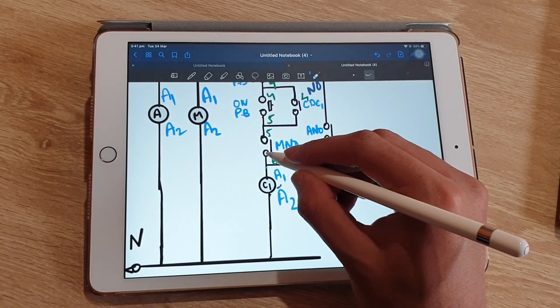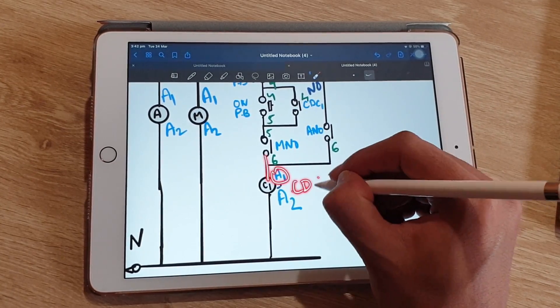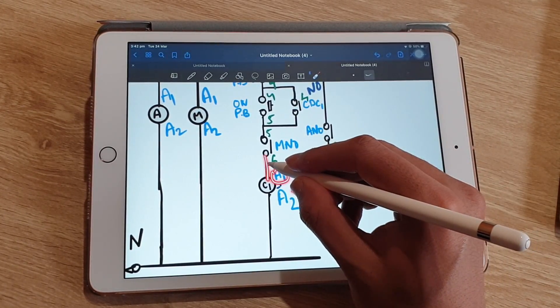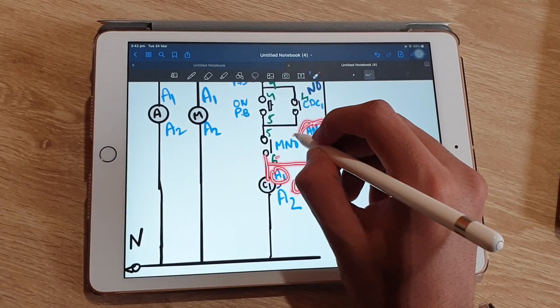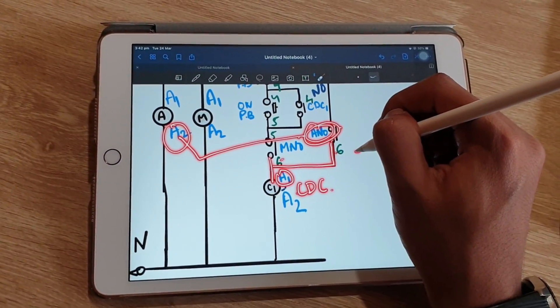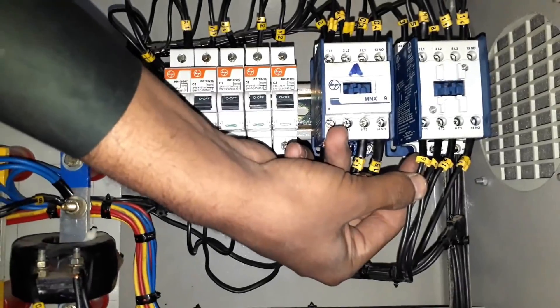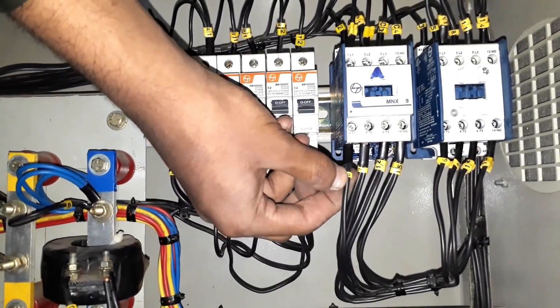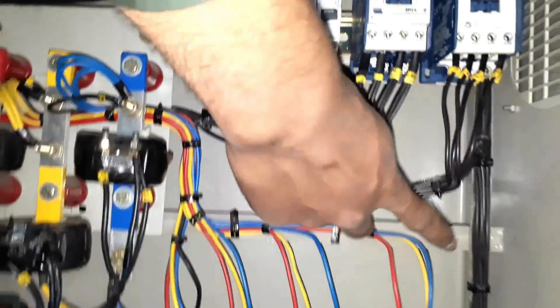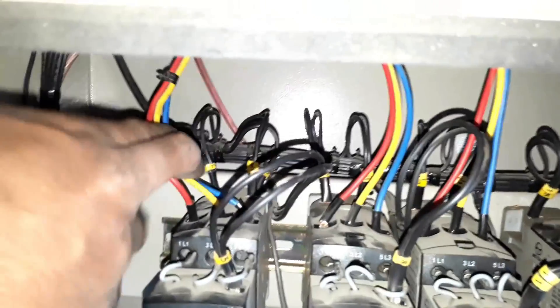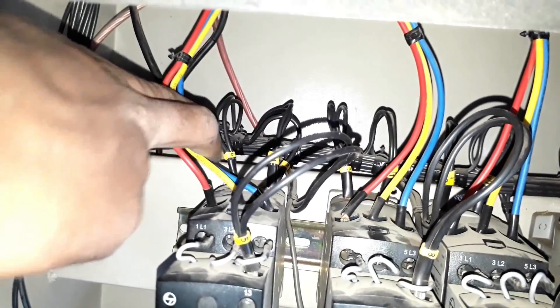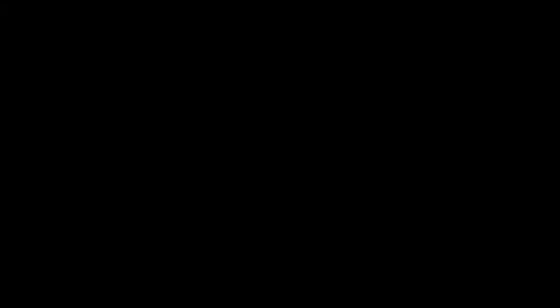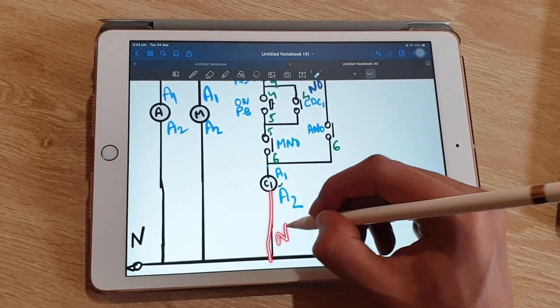From terminal number six of the manual NO, two wires are taken out and connected to A1 of the capacitor duty contactor as well as to the NO of the auto contactor. From the NO of the manual contactor we are connecting to the NO of the auto contactor, and from the NO of the auto contactor we are connecting to A1 of the capacitor duty contactor. The A1 terminal of the capacitor duty contactor is tagged as six, and the A2 terminal of the capacitor duty contactor is connected to neutral.